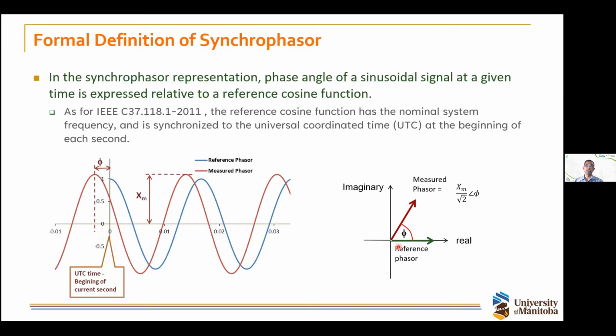The second thing is that the peak of this cosine signal coincides with the beginning of the UTC second. UTC is the Universal Coordinated Time, the time standard used worldwide. Whenever a new second starts, that point coincides with the cosine signal. So if there are 50 or 60 hertz, after 50 or 60 cycles, when the next second begins, it should coincide with the beginning of the next second too, if everything is correct. Then the phase angle of any other signal is expressed with respect to this reference cosine signal.